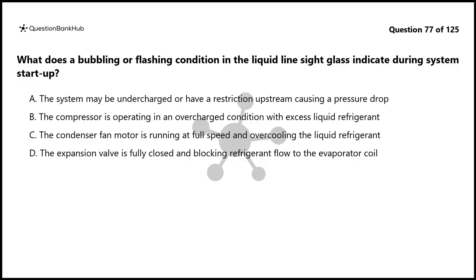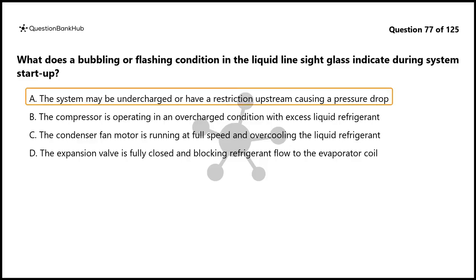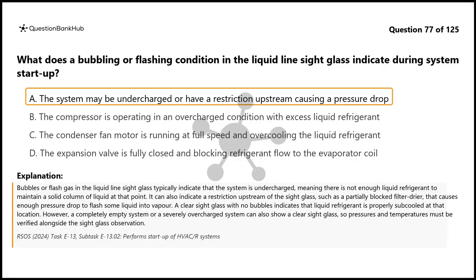The correct answer is A. Bubbles or flash gas in the liquid line sight glass typically indicate that the system is undercharged, meaning there is not enough liquid refrigerant to maintain a solid column of liquid at that point. It can also indicate a restriction upstream of the sight glass, such as a partially blocked filter dryer, that causes enough pressure drop to flash some liquid into vapor. A clear sight glass with no bubbles indicates that liquid refrigerant is properly subcooled at that location. However, a completely empty system or a severely overcharged system can also show a clear sight glass, so pressures and temperatures must be verified alongside the sight glass observation.